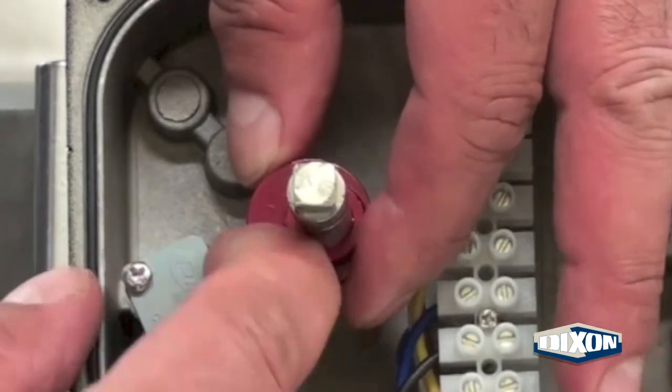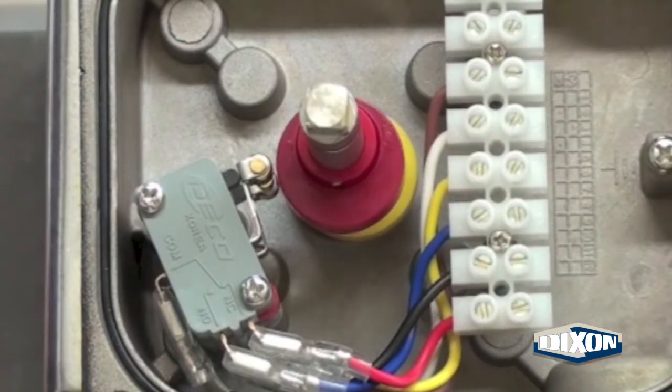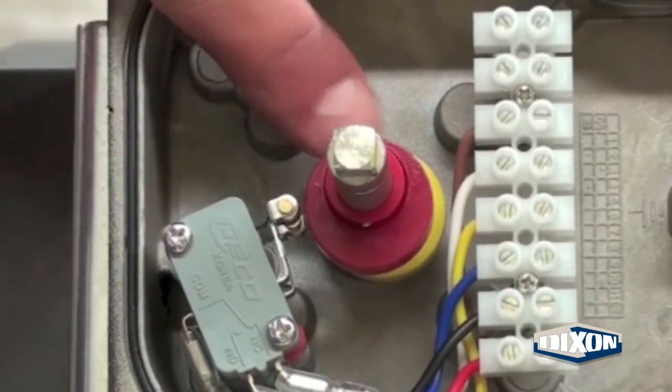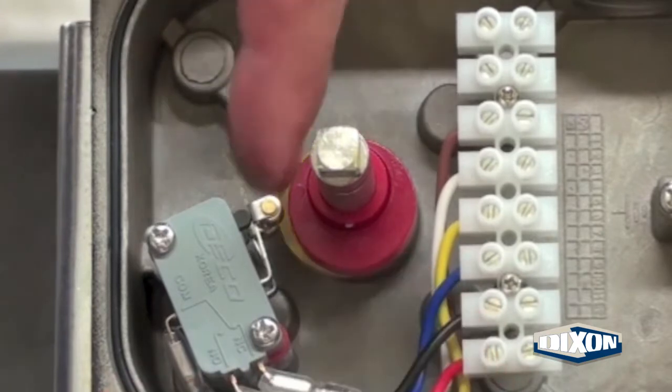When the valve is closed, the red cam should depress the upper switch. Open the valve to set the yellow open cam. To set the lower cam, lift away from the splines and rotate so that it depresses the lower micro switch.